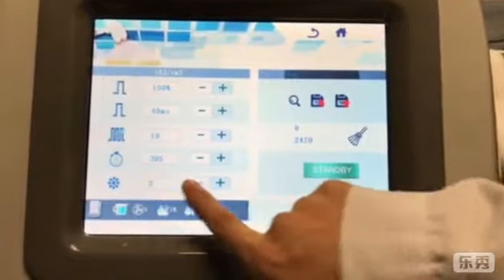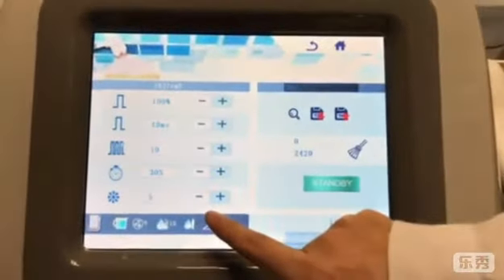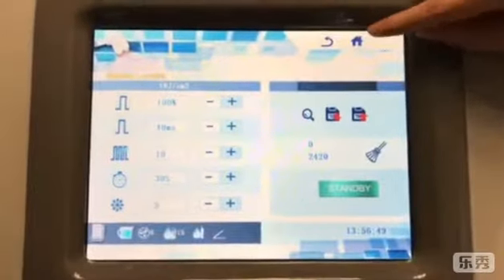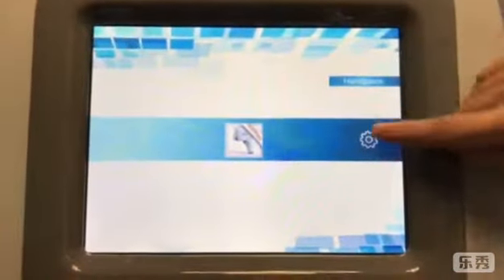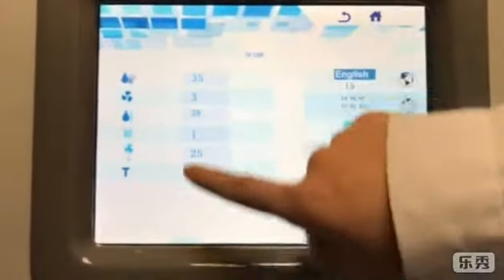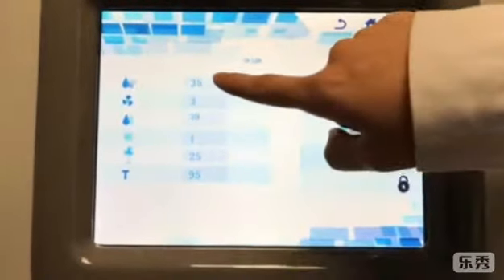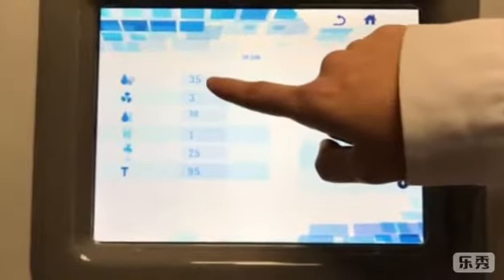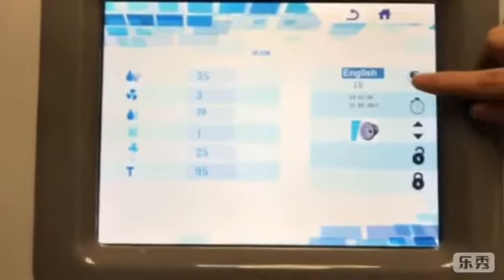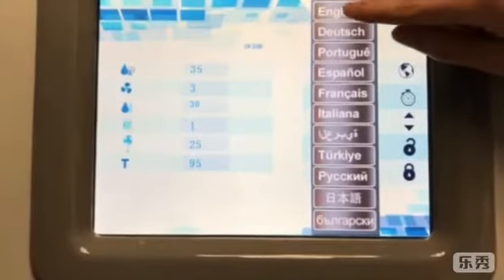Cooling level from level 1 to level 5. With level 5 you can reach minus 20 degrees very quickly. In the settings interface, you can change the alarming parameters — for example, if the water temperature is more than 35 degrees it will start alarming, same for other parts. From here you can change language — 11 languages available. That's all, thank you.